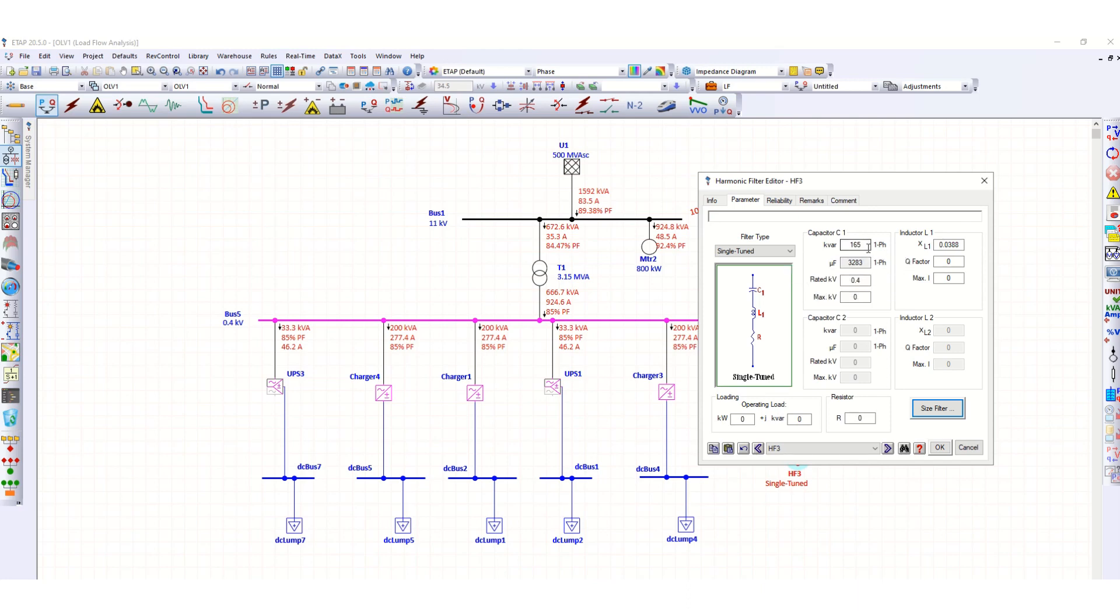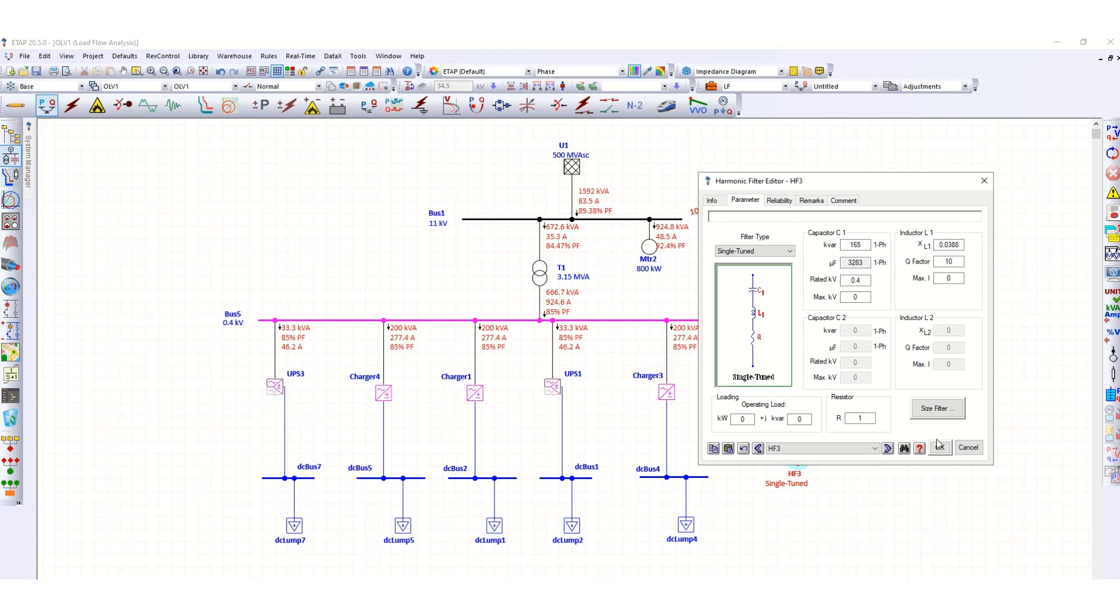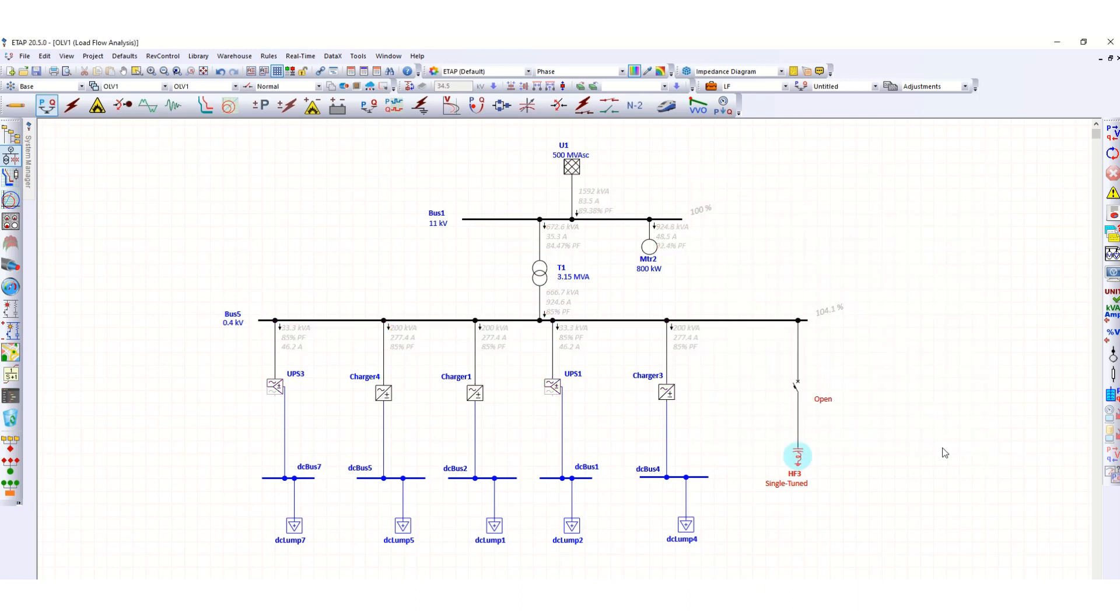Now you can see the value of C1 and L1. These values are substituted as per the filter size whatever we have just now done. Now this Q factor we have to mention. Since this is single tuned filter, C2, L2 are not required. Let's put the value of R, suppose 1 ohm, and now click OK.